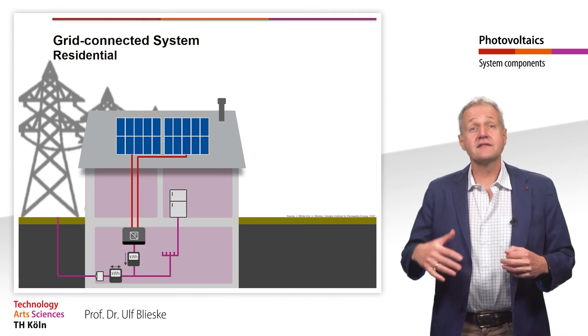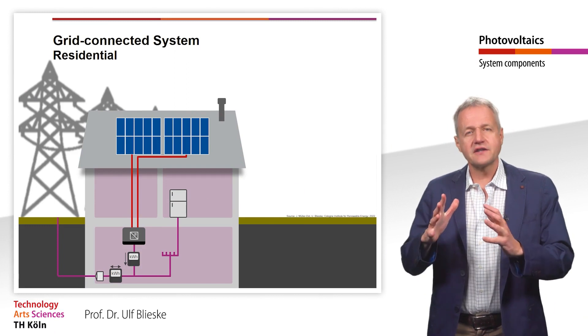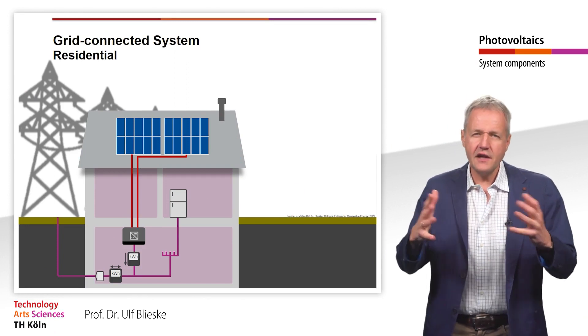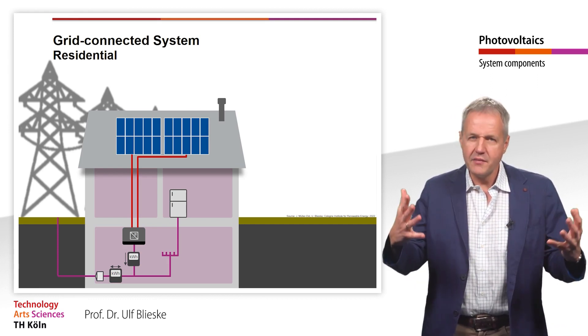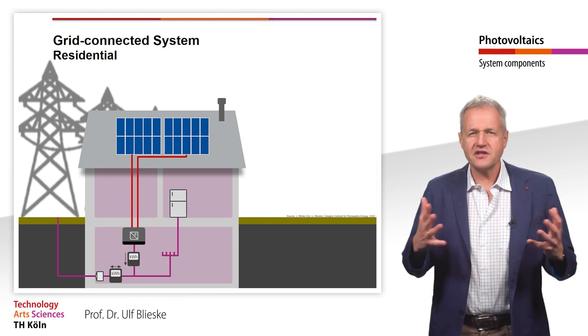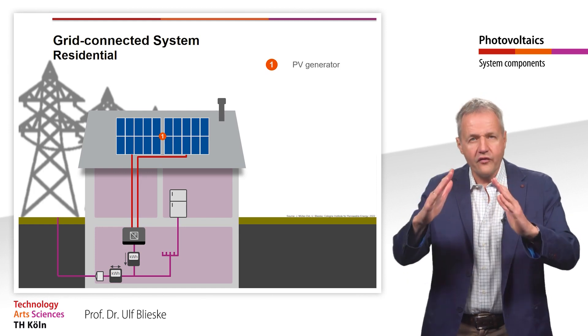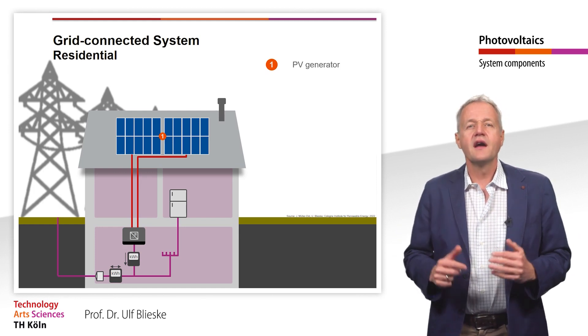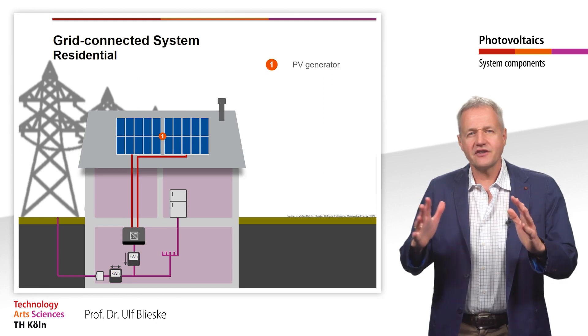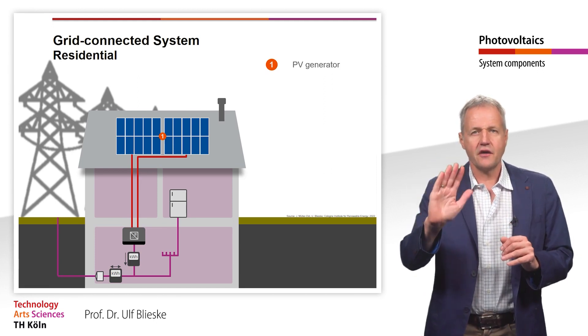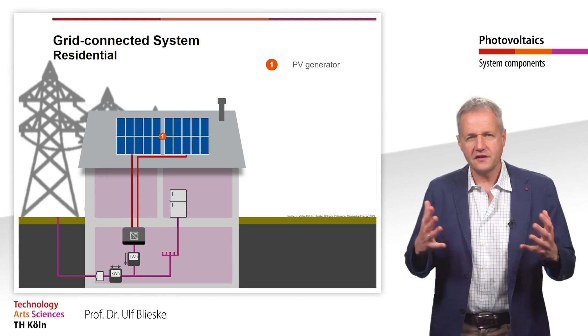Furthermore, there is a large and steadily growing number of rooftop installations worldwide that are connected to the public grid. Here you can see a typical grid-connected PV system as it can be found on many millions of roofs around the world. In such a system, the PV modules are typically installed on the roof using a special mounting system and are connected in one or more strings depending on the generator size and orientation of the modules. A generator connection box is only used in some of the installations.